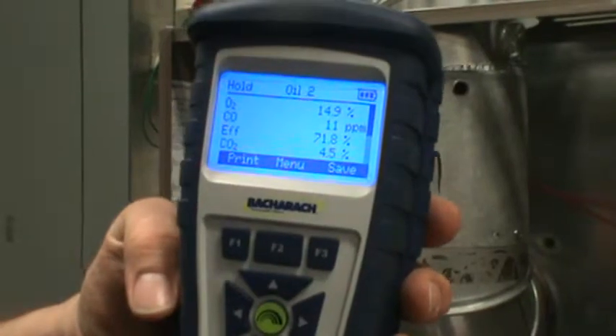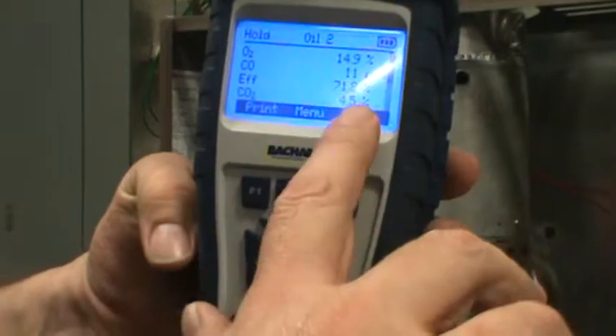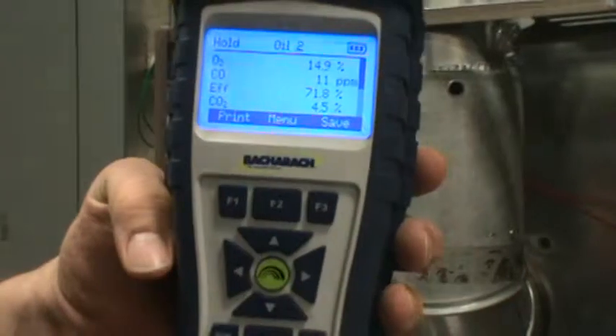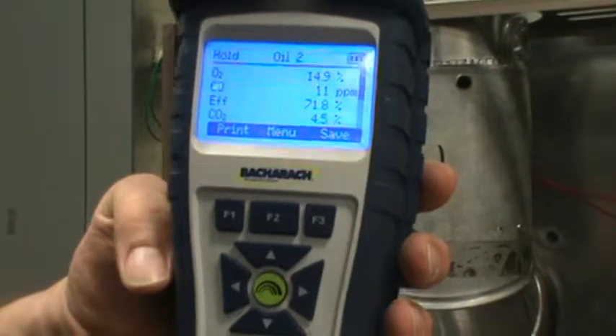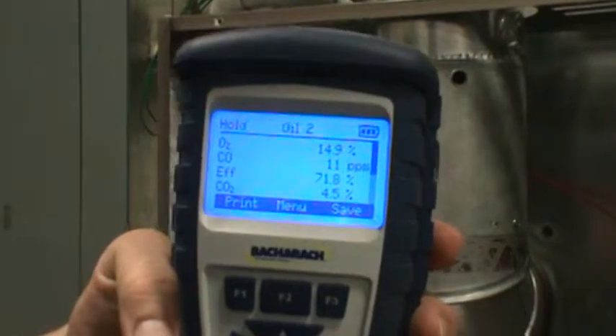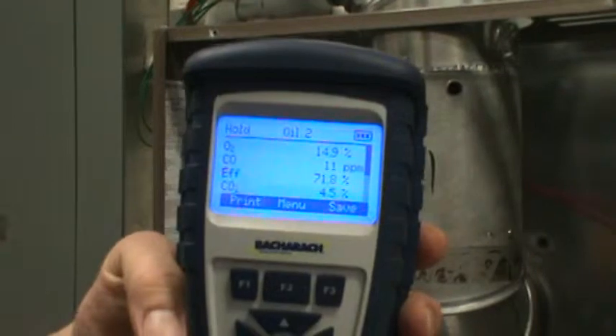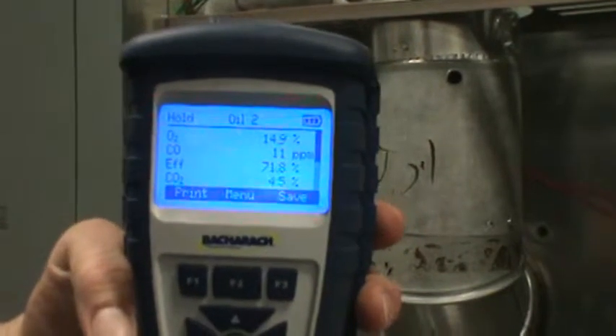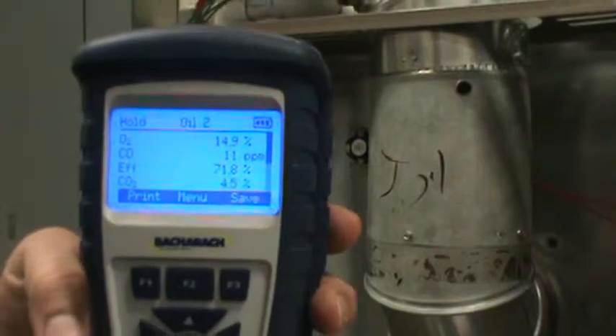I'm getting a number of 14.9, which is a little high in my oxygen. And there's some parameter sheets you can get, but you can also tell just by looking at this, that the efficiency is only my SSE, my steady state efficiency, which is the on-cycle loss, is only coming up at 71.8%. That's not good for an oil-fired furnace of this age. A modern oil-fired furnace should be somewhere between 82% to 85% on the steady state efficiency. Those are typical for a modern oil-fired furnace. So our SSE is kind of low.